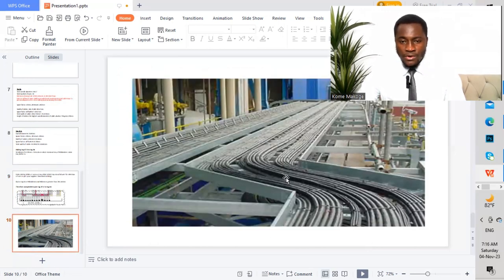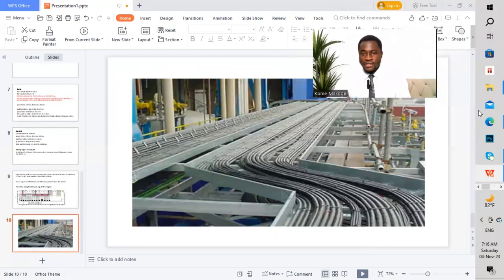This is our cable tray now installed on site, and we lay all the cable trays to ensure that we have the spacing that we require, as well as the space factor, which is very important. While we are carrying out the installation, we get an approval for our cable tray size that has been selected. We should also have an approval for the installation on site. So we've proved and ensured that for the size of cable tray we have for TAC 16, we can now mesh TAC 17 into TAC 16, which is very important.